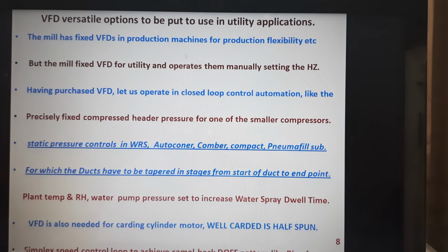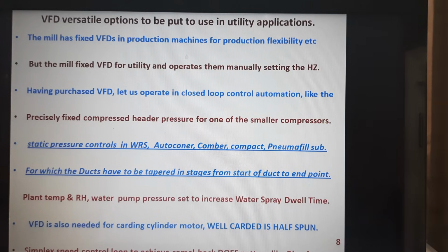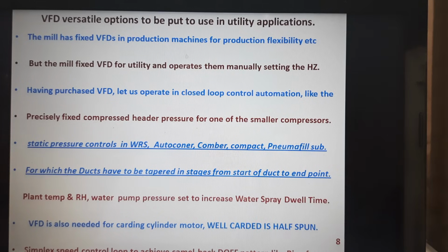Coming to the plant temperature and RH for the given plant, this also needs to be in closed loop control. It can have a band, but definitely closed loop control will help the mill as such. The water pumping pressure needs to be around 1.5 to 3 kg, but still a VFD on the water pump pressure control definitely helps to increase the spray dwell time of the water mist inside the AC plant, so that you can maintain more than 95% RH at the mist eliminator, and definitely this is carried over to the mill side.